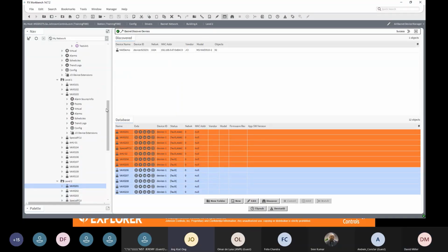Yep. So if we are using the IP VAV, the 1930, is it possible to use a TE730 as a SA bus device? Yes. How do we do that? Because for the 1930 it's a 6-pin and for the TE730 is an 8-pin. Yeah.